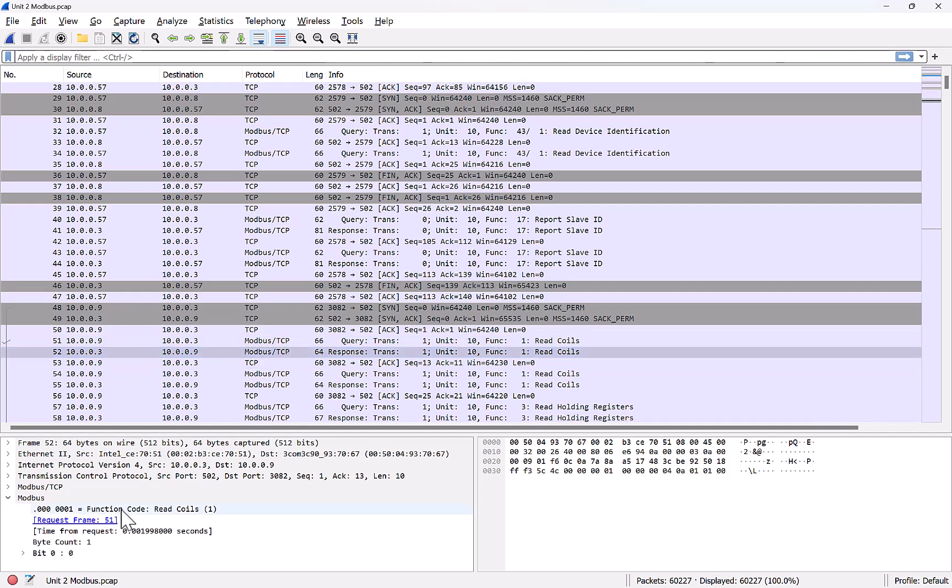Well, that's great because now we start to be able to build that picture of what's out there on the network. So if we didn't know that there was a system at 10.0.0.3 before, we do now. And we can even see it responding on the next line with a response from that coil read. And we can even jump down because of the parser, and it even shows us the value of the coil that was read was a 0. Remember, the value is either going to be 0, 1, on or off, true or false.